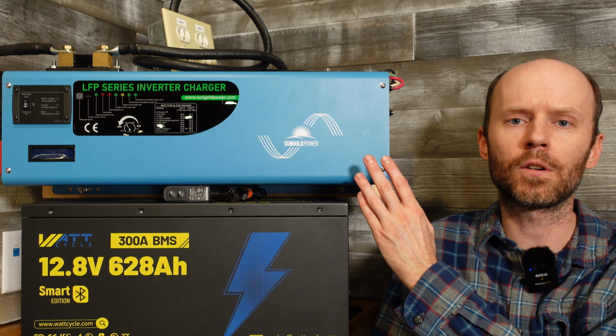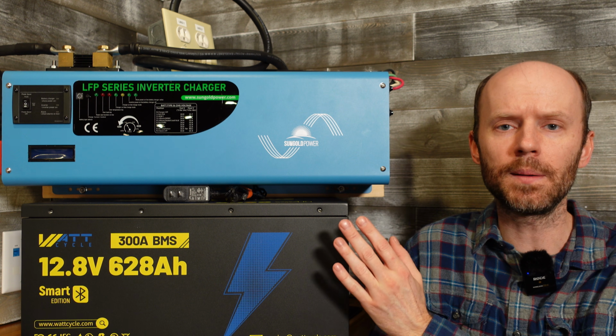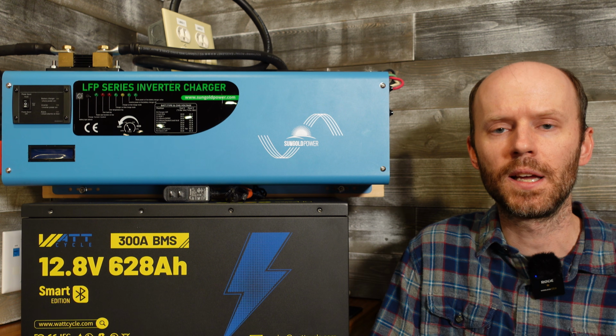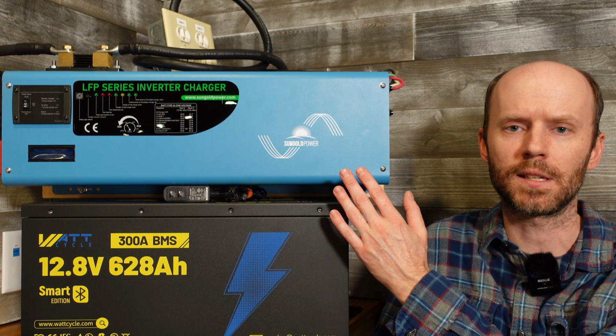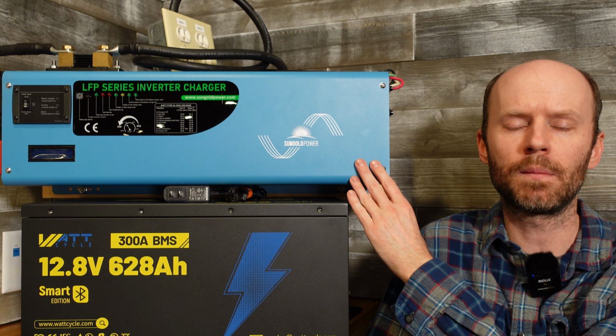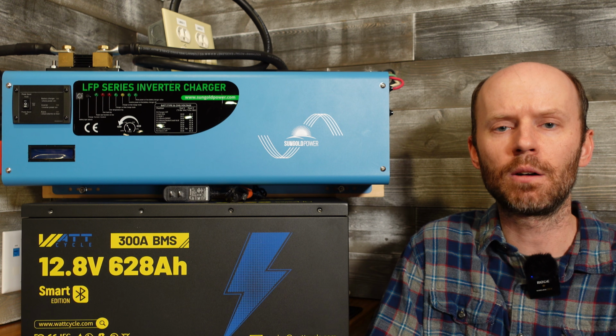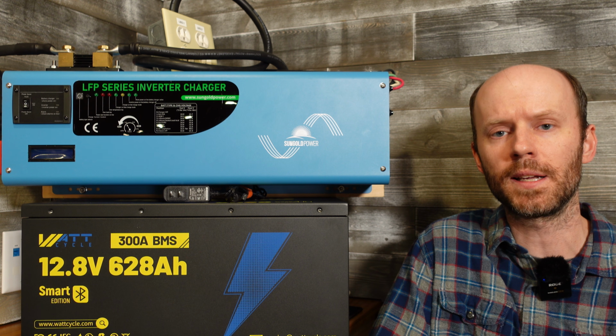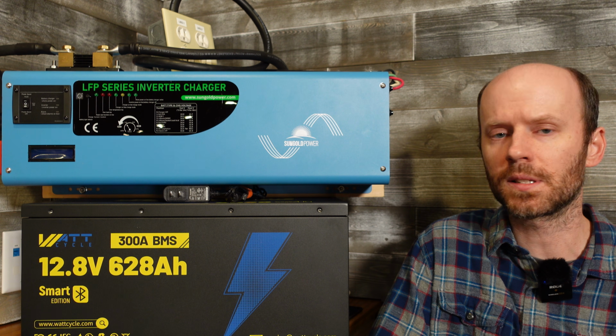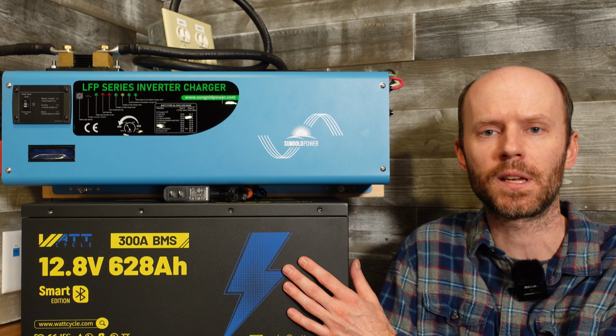The lowest this inverter will operate is 10 volts, and sometimes these batteries go below 10 volts, in addition to considering the losses in these cables. I do expect this inverter to shut down before the BMS in this battery does. However, it should still give us a reasonable capacity value. And the purpose of this test is more so to see if the battery can handle the current.